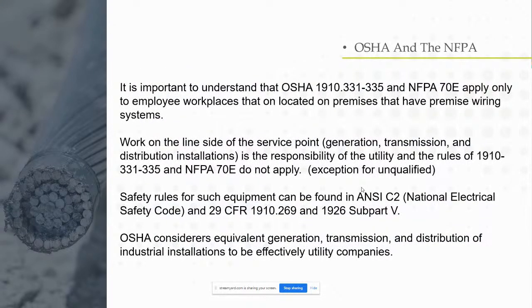Once you get into 70E and look at the introduction, it talks about how subpart S and 70E apply only to the employees' workplaces, basically premise wiring. Work on the line side or the service point is the responsibility of the utility, and 331 through 335 in 70E does not apply.